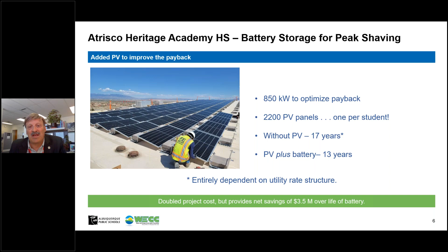So the asterisk in the without PV is important for this discussion, because the savings on this peak shaving battery system were entirely dependent on the utility rate structure. In other words, we were doing it for financial reasons to reduce peak demand and the charges associated with it. But if the rate class changes and the criteria for when you get charged change, which is happening quickly with more distributed energy on the grid, then that changes the payback drastically. When you add battery and solar together, suddenly you can use anything anytime you want.